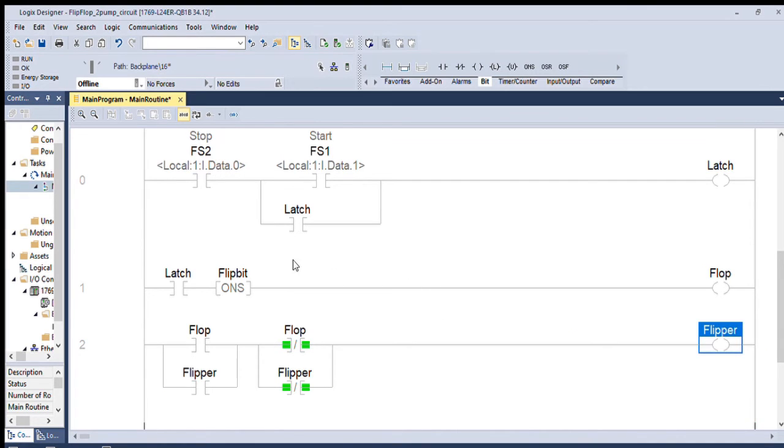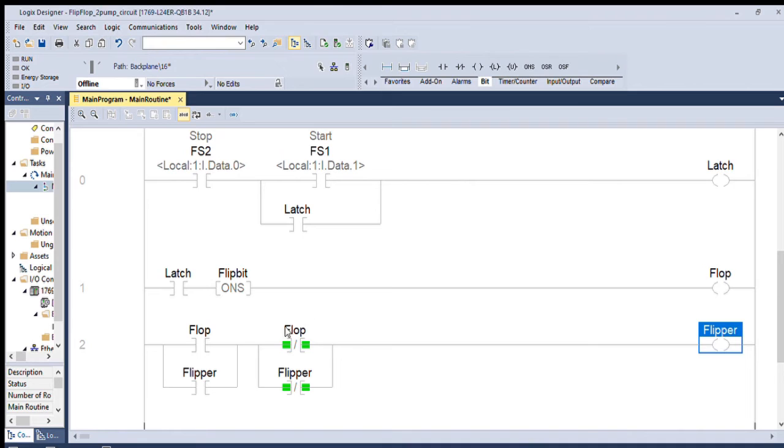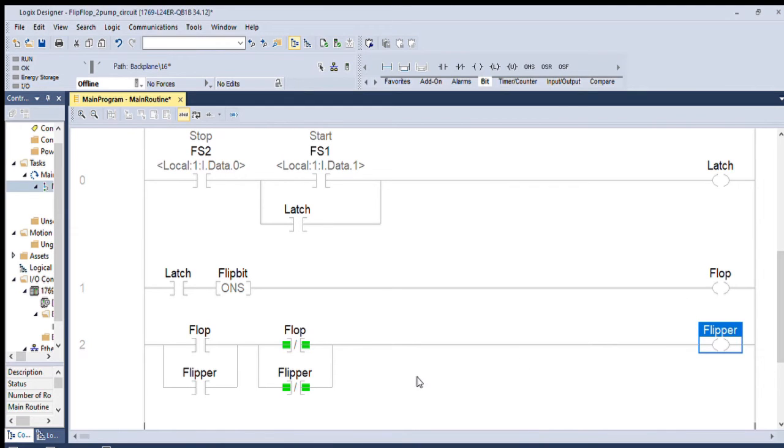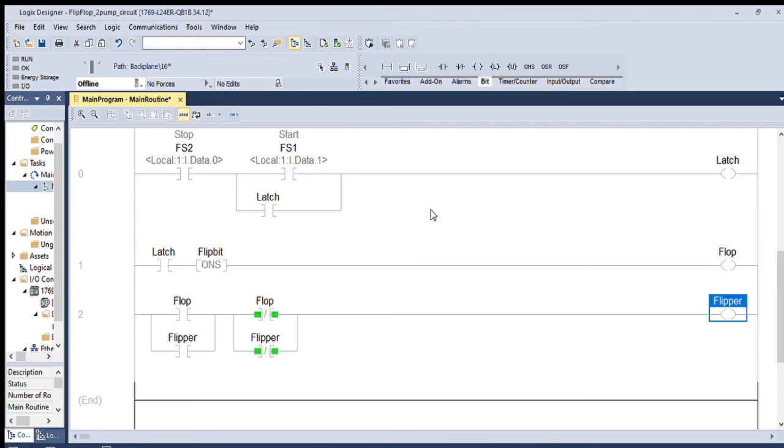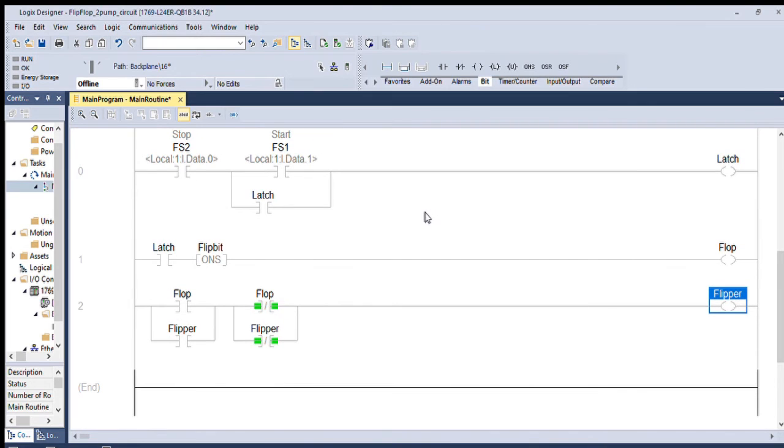So as the one shot goes through, it'll hit the flop. The flop will give it a quick shot. But since this one and this one is good, it won't have time to catch this one, because it won't change that one until the following scan cycle. And that'll trigger my flipper. And then on the next scan cycle, when it updates the outputs, then it'll change. It'll change this guy right here. So let's take a look. Now, that is my basic flip flop circuit.